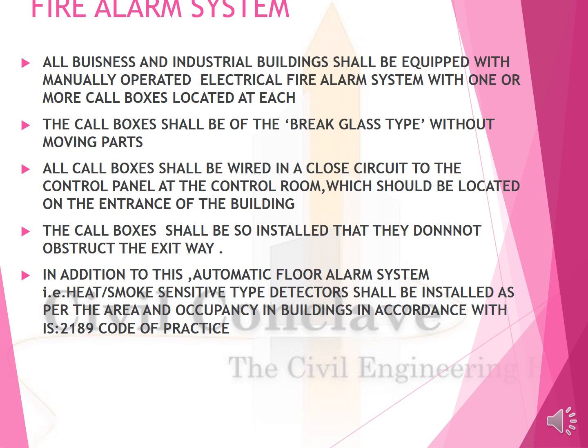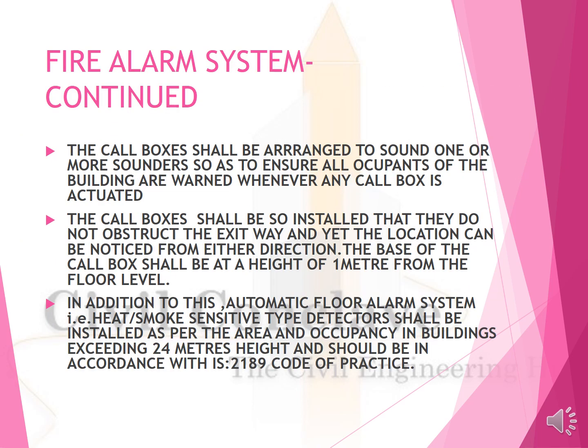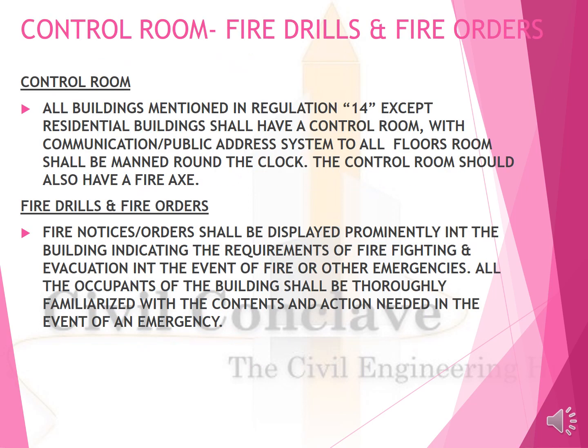In addition to this, an automatic fire alarm system, that is a heat and smoke sensitive system, should be installed as per IS 2189. The call boxes shall be arranged to sound one or more sounders so as to ensure that all the occupants of the building are warned whenever any call box has been activated. Control room. All buildings mentioned in regulation 14 except residential buildings shall have a control room with a communication and public address system to all the floors, manned around the clock.